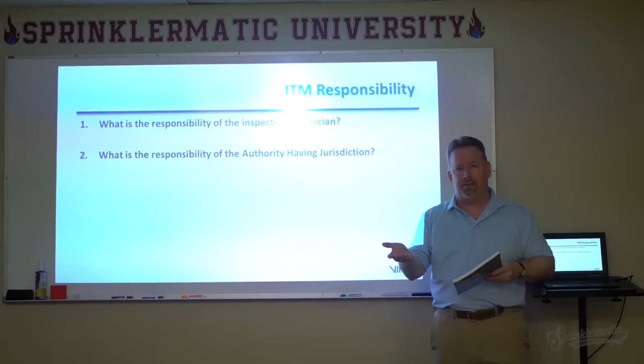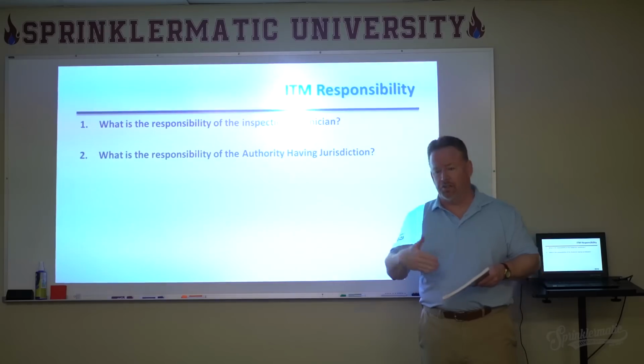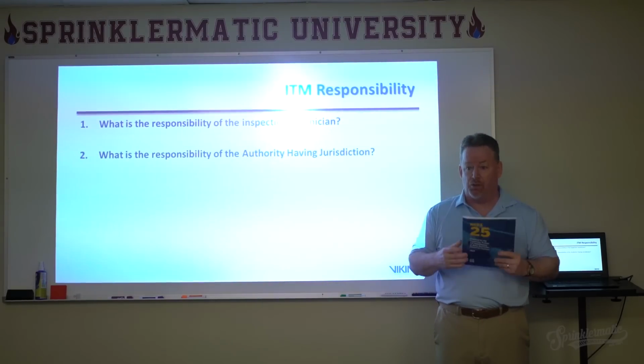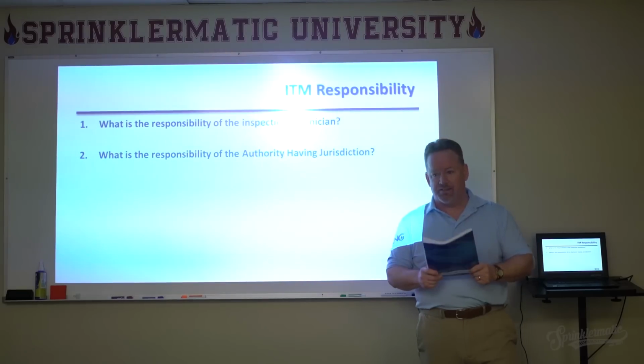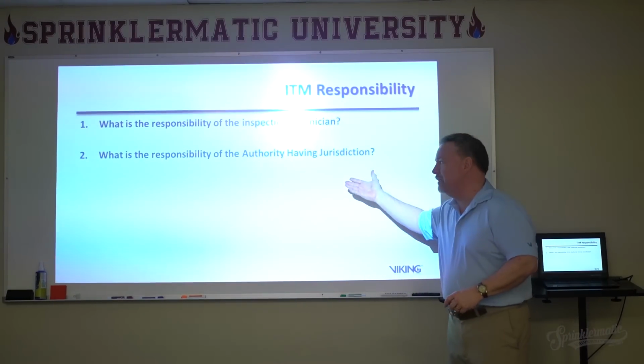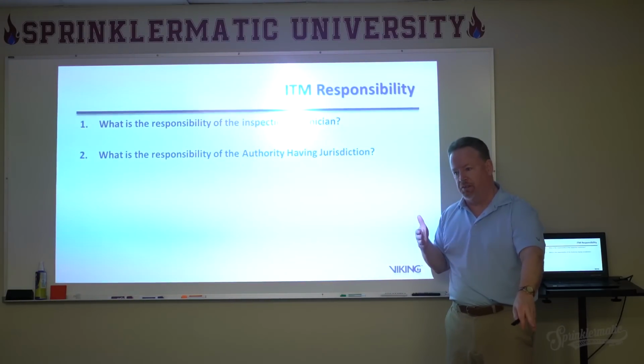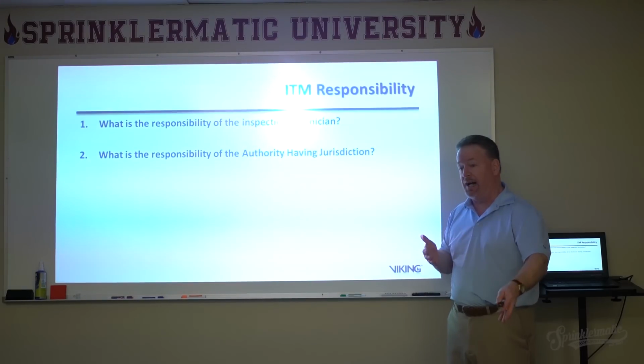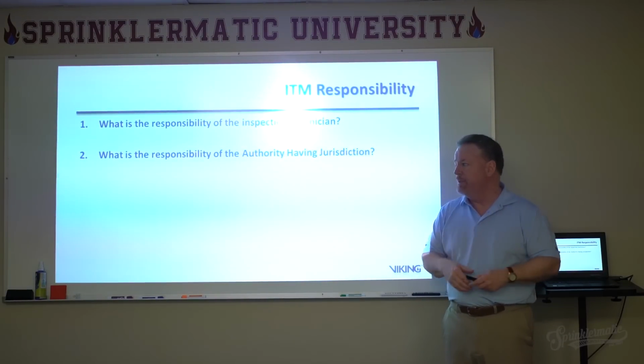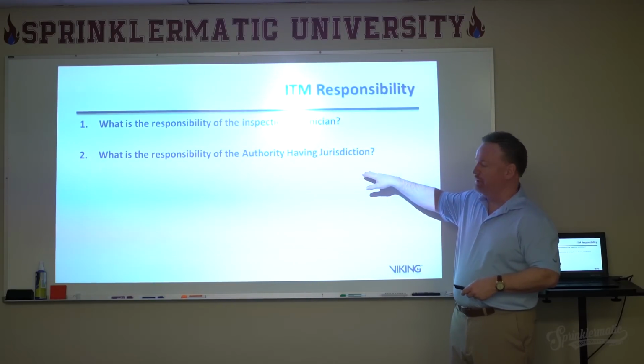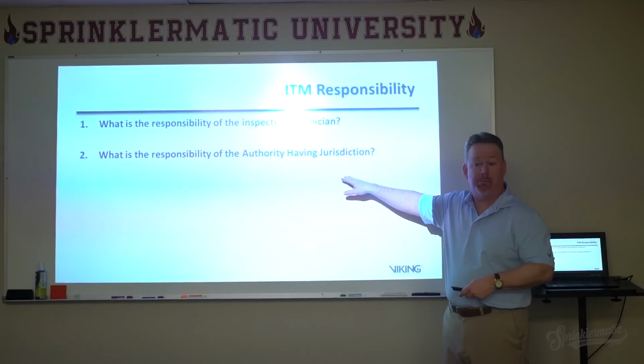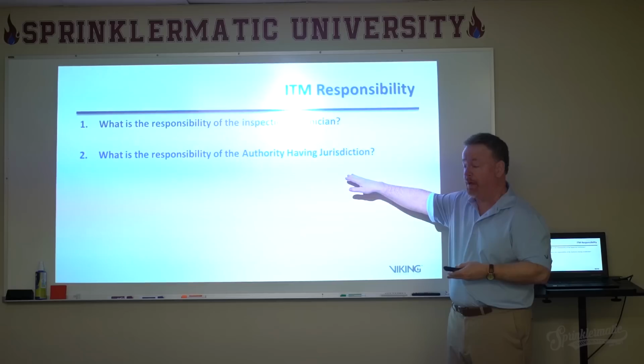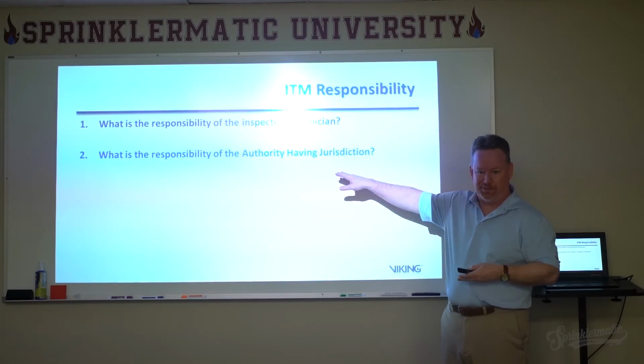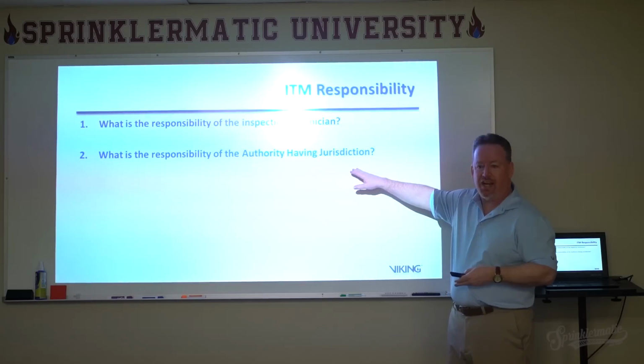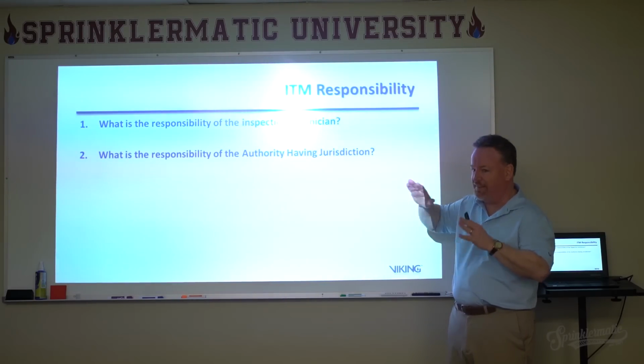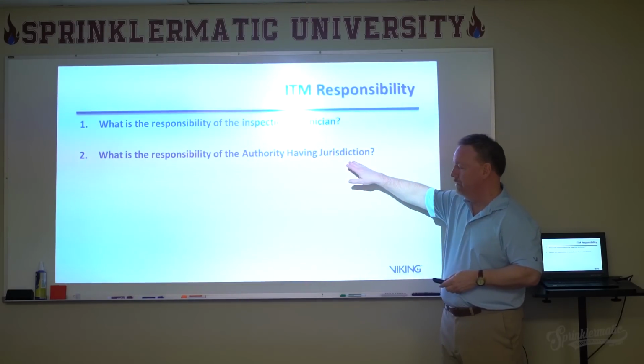Their responsibility is enforcing the law that says NFPA 25 is the document owners must use to inspect, test, and maintain their systems. So they have a responsibility under the administrative law of the state to make sure the law is being applied and owners are obeying it. This becomes tricky, because any authority having jurisdiction will tell you they don't have the manpower—myself included, as a former fire code inspector—to get into all the buildings with all these systems. It's a big challenge for them, but that doesn't change the fact that enforcing the law is their only job.